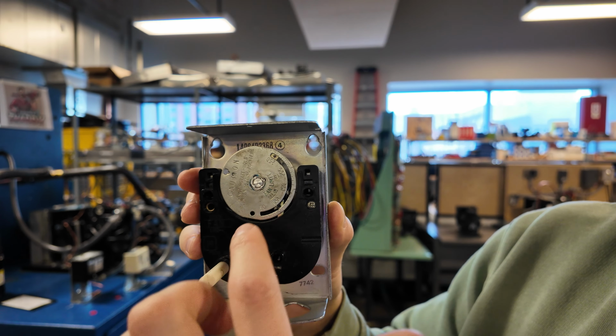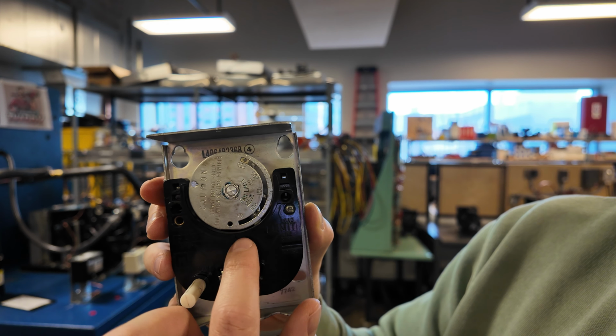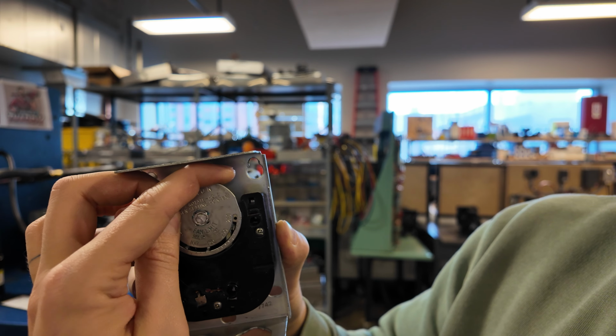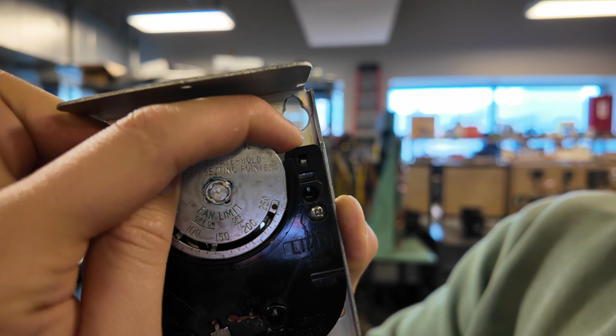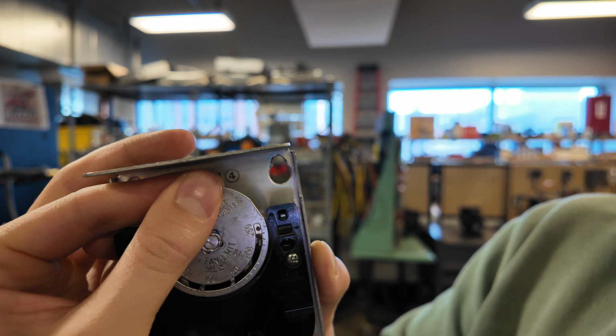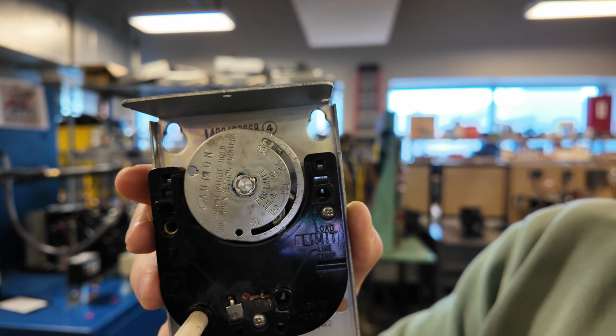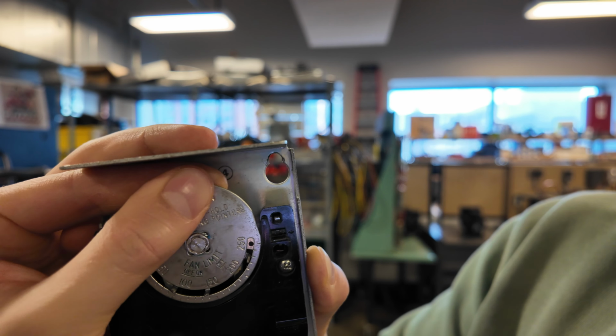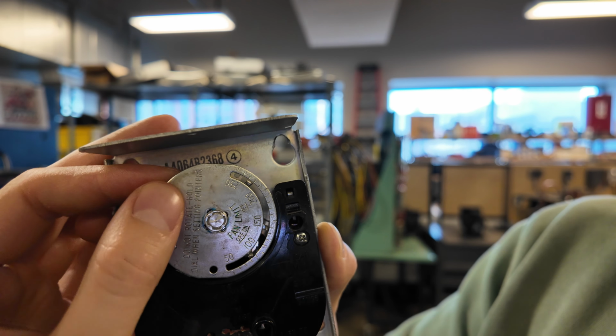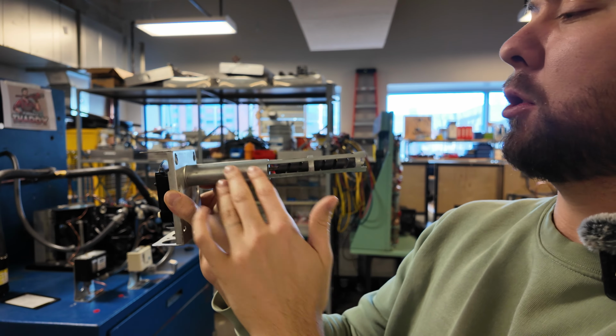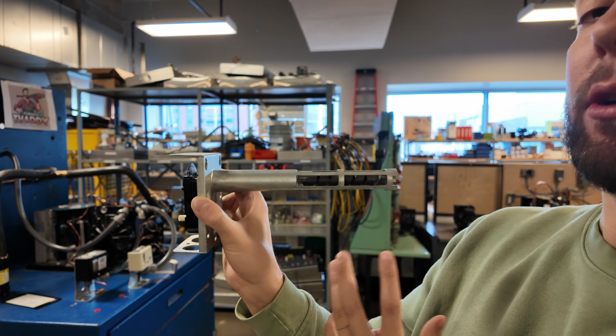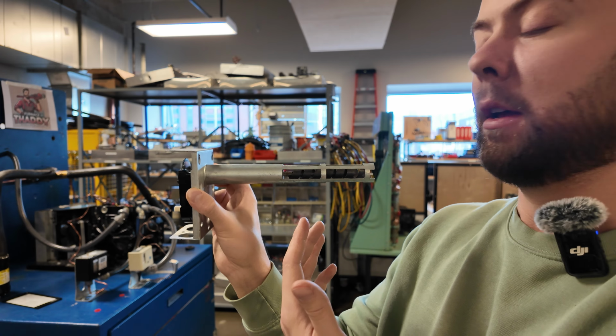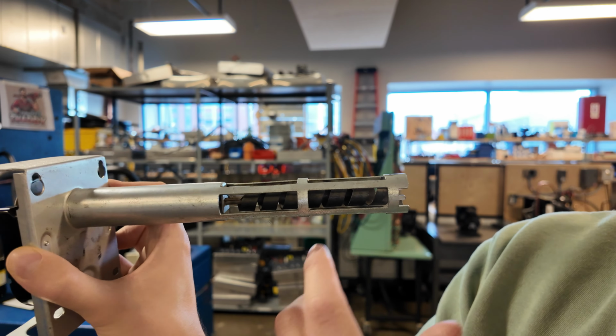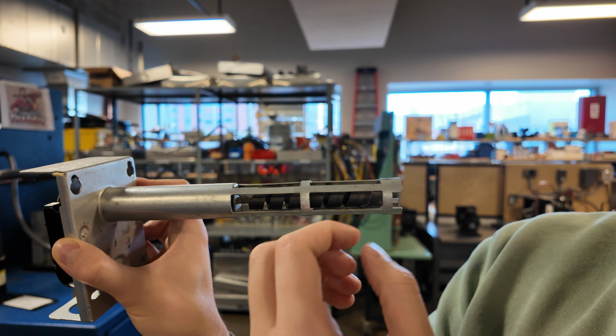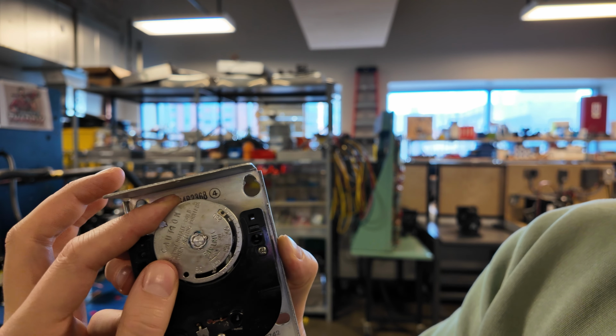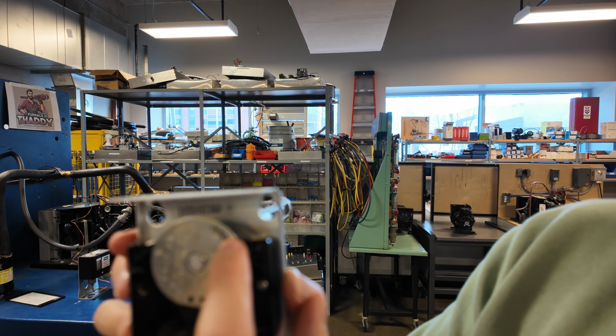Once the heat exchanger warms, it's going to spin this dial. It's going to hit near the arrow here, and when it hits, it's going to energize the blower. Okay? And let's say there was an issue, so we had a faulty blower motor. Now it's going to turn, energizing the blower, but the blower might not actually energize. So the temperature in the heat exchanger, where this bimetal strip is reading, is going to keep increasing because we can't cool the heat exchanger, because the blower's not working. So this strip would get hotter and hotter, and the thermal expansion would go up, and it would turn the spiral, which then turns this head, and it's going to keep twisting until it hits the third arm here.